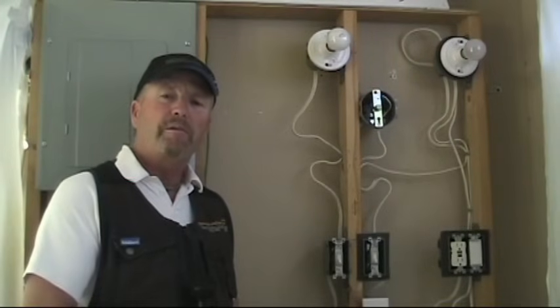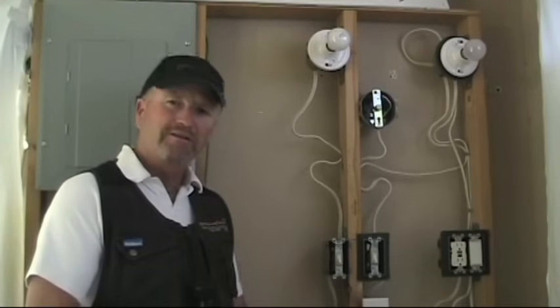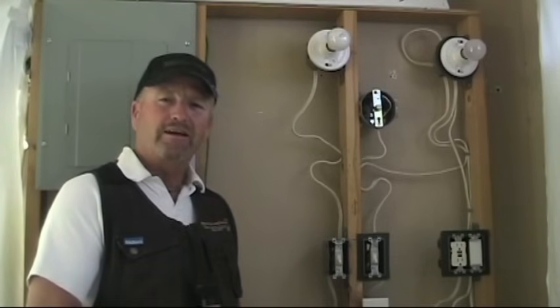So I'm going to set up the situation that Rob had and using my meter I'm going to show you why he had 120 volts on his neutral and what you have to do to correct that, starting with shut off the power when you're working with electricity.